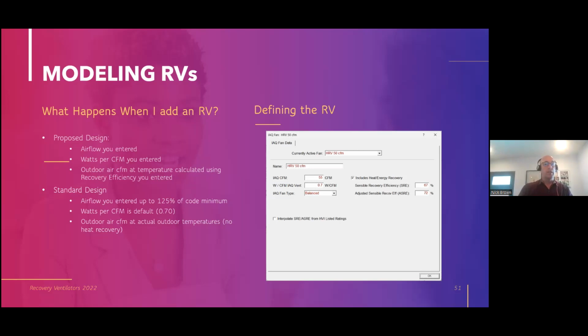The standard design is going to have a default 0.7 watts per CFM, and the outdoor air is going to come in with no heat recovery. That's where we open up our compliance margin.